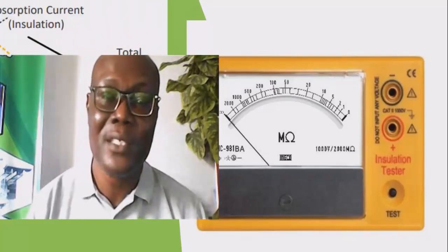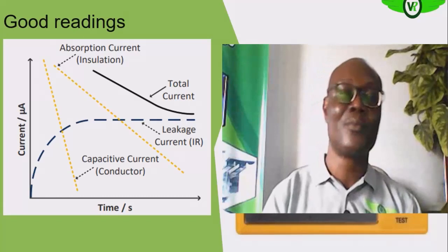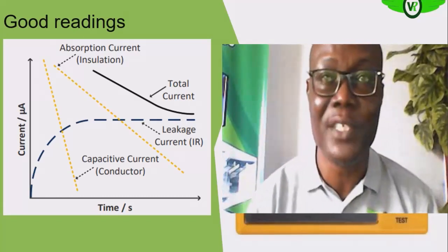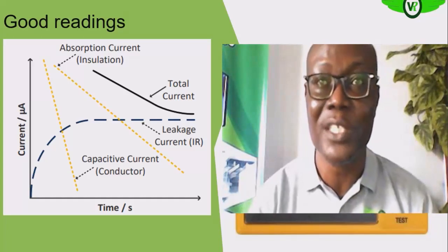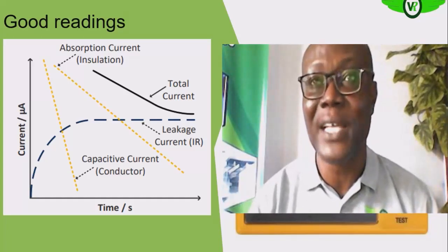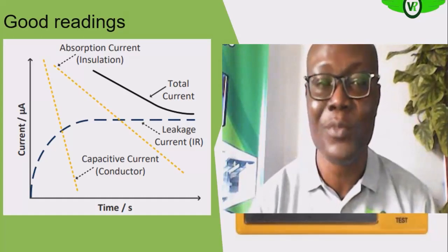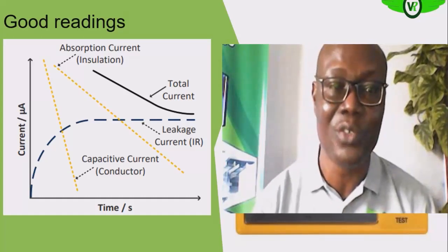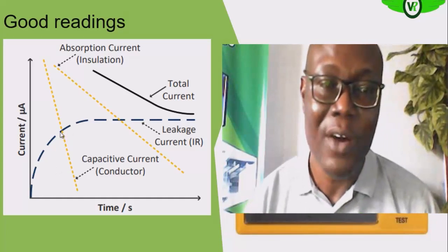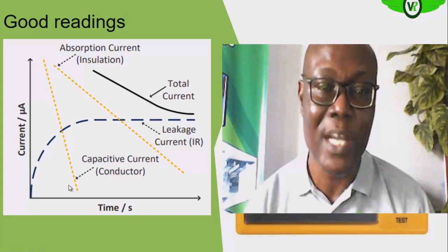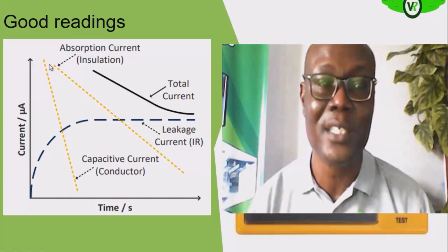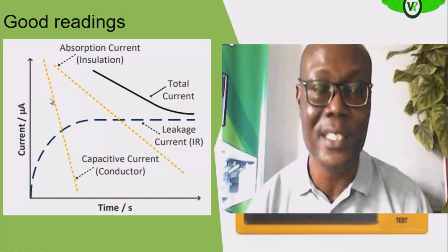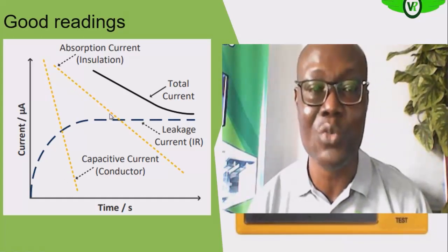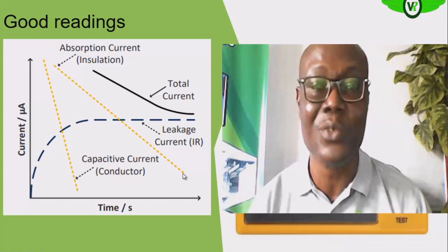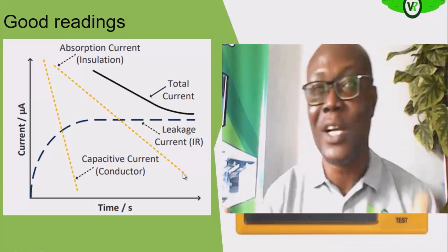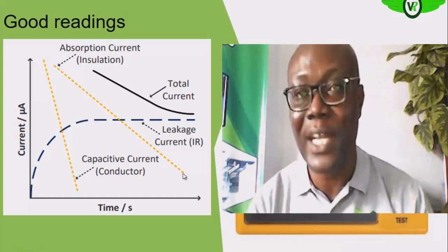So how do we determine good reading, or how do we take good reading? Remember, we have identified that we have three different current components when we apply that potential between the insulation when taking our IR test. So this is the capacitive current. Like we said, you see that it is high initially, then it decays after a few seconds. The absorption current too, you see, it takes a longer time for it to decay because it takes much longer time for the dipole to realign, as we saw.